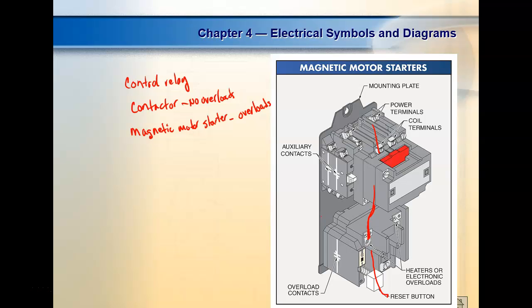But the overloads allow the motor to pull over its run current for a certain amount of time. So it'll allow it to do what? It'll allow it to start. But if it stalls or it doesn't start, then it'll kick out your control circuit. Are we okay? That makes sense?